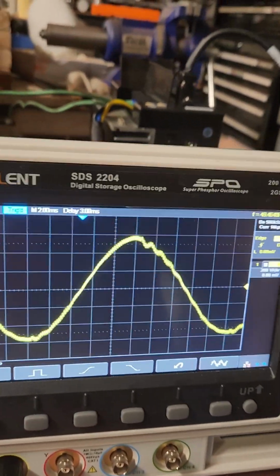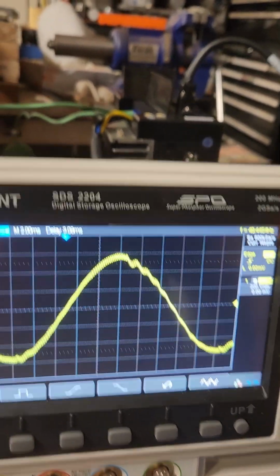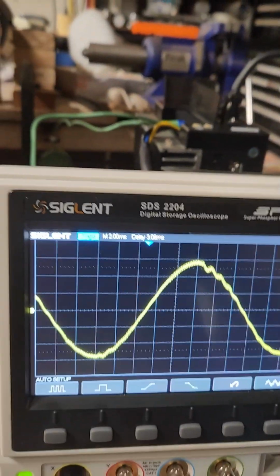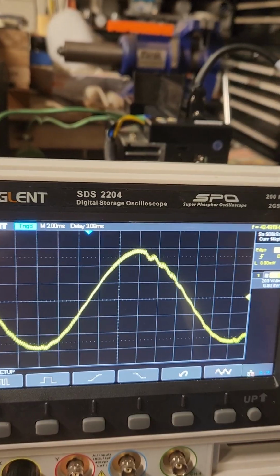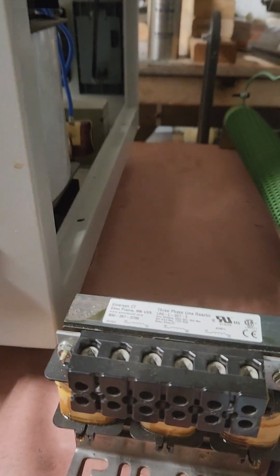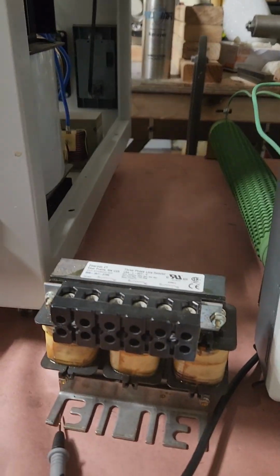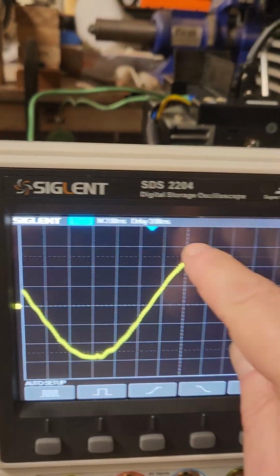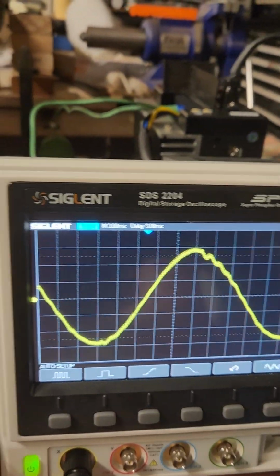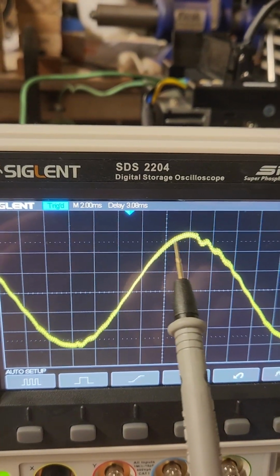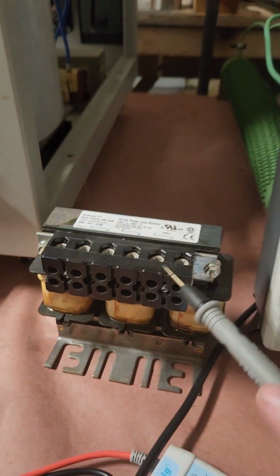I don't think that counts too much, because the input in the drive is a bridge rectifier followed by a capacitor bank. I think I'll also try using this line reactor, 30 amps, I measured it at 360 microhenry for each. I'll put this in to see if there's any improvement. That 40 volt swing I measured at the top with the cursors should drop to about 25 if I add this.